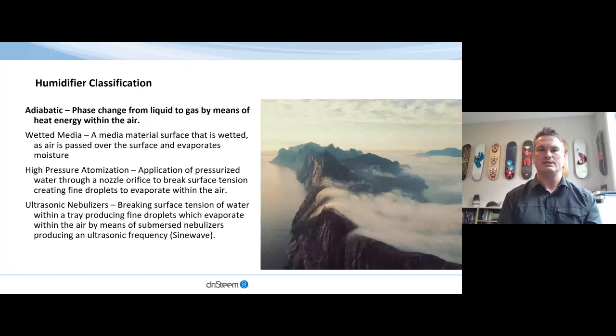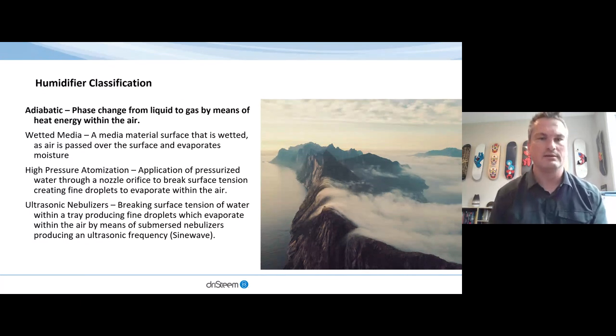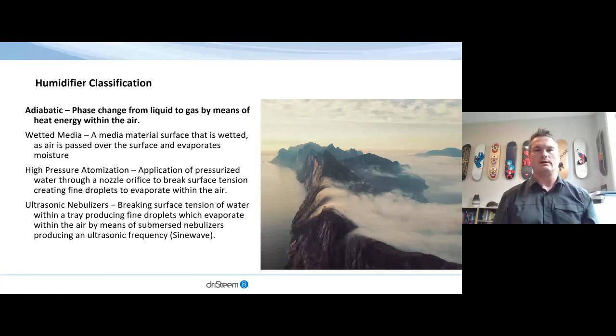Also, high pressure atomization. This is where we take water, pressurize it to around 1,000 psi, and push that water through a very small orifice in a nozzle to break surface tension and create very small droplets. So a misting or a fog, as you'd like to call it, and those fine droplets are easily evaporated within the airflow. Also, ultrasonic nebulizers are another method, where breaking the surface tension of the water is done in a tray, with a nebulizer operating at an ultrasonic frequency, creating very small droplets in a fog, which can be carried through the air and evaporated and collected through that air.